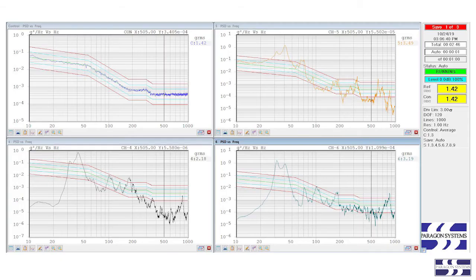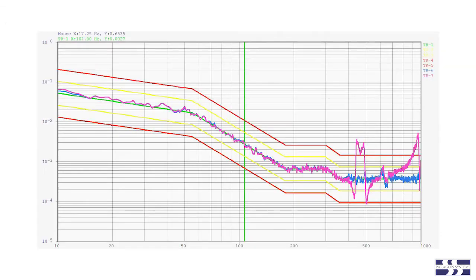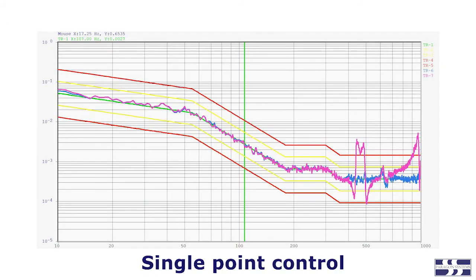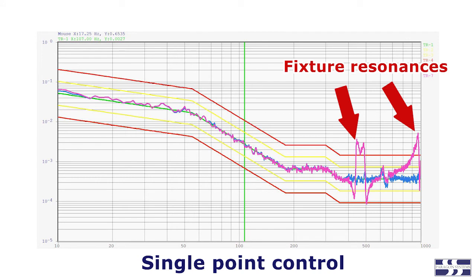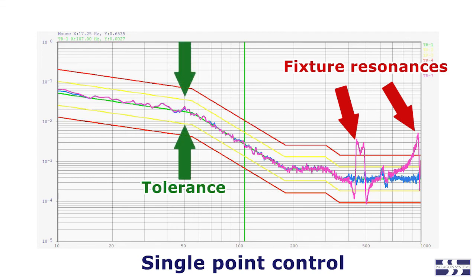Controllers can average the output from multiple accelerometers in a technique appropriately called averaging, and use this signal to control the armature. Averaging can be used to mitigate some of the negative consequences of vibration fixture resonances.